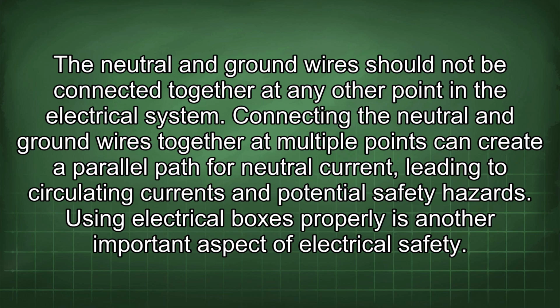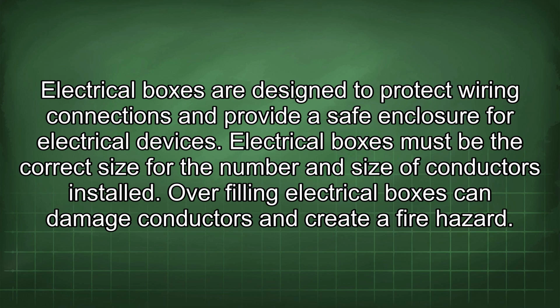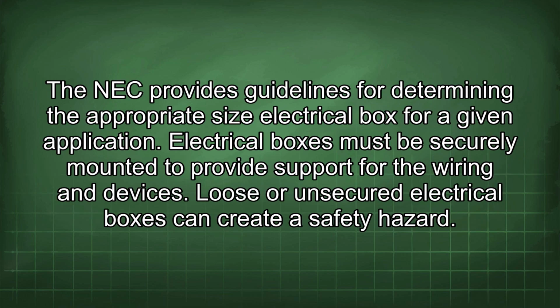Using electrical boxes properly is another important aspect of electrical safety. The electrical boxes are designed to protect wiring connections and provide a safe enclosure for electrical devices. Electrical boxes must be the correct size for the number and size of conductors installed. Overfilling electrical boxes can damage conductors and create a fire hazard. The NEC provides guidelines for determining the appropriate size electrical box for a given application.